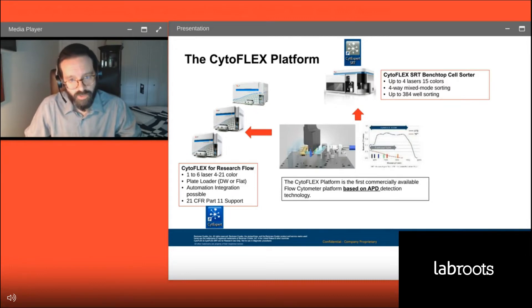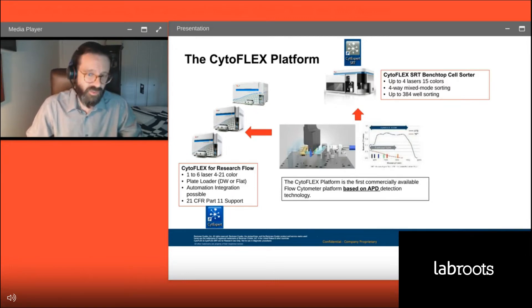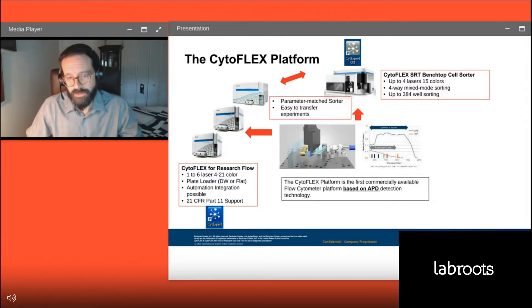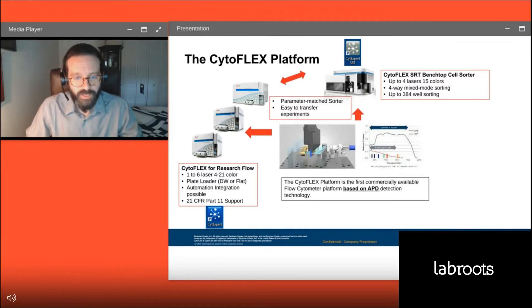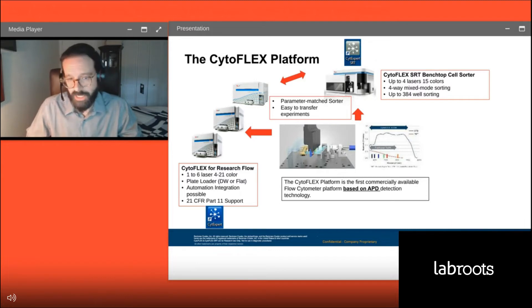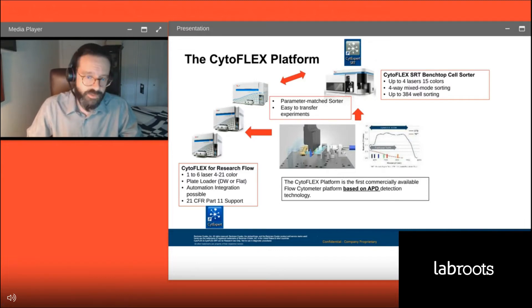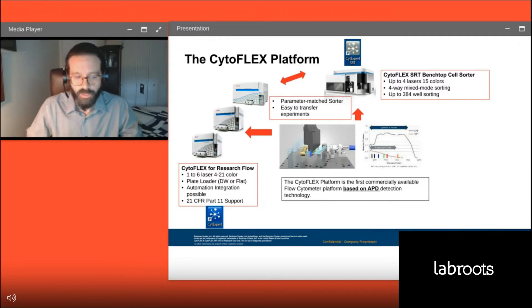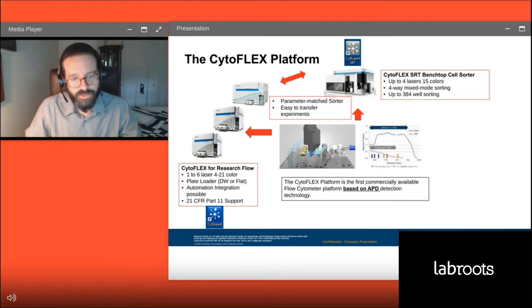With the SRT, we top out at a four-laser, 15-color system with four populations total possible to sort, mixed mode sorting capabilities, and the ability to sort in up to 384-well plates. These are also easily parameter-matched to analyzers — when you have a laser and bandpass match between your analyzer and your sorter, you can easily transfer experiments between them without having to redraw regions or recreate statistics.